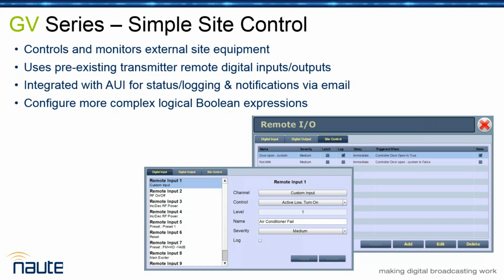A couple that I've encountered. One was really cool: a site where they run their generator on a weekly test, and they have a specific generator mode set up for the transmitter. But during the test, when they're not doing a full load test, they didn't want the transmitter dropping power just because the generator status was active. So they put a little AC relay, basically an AC detector, and used the Boolean expressions in the site controller, so if the AC was on and the generator was on, the transmitter stayed at full power.